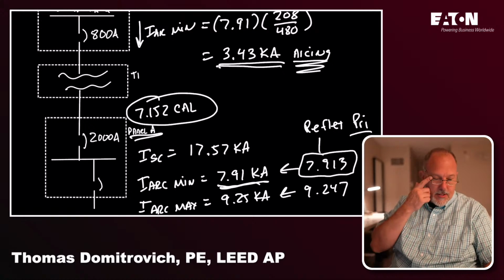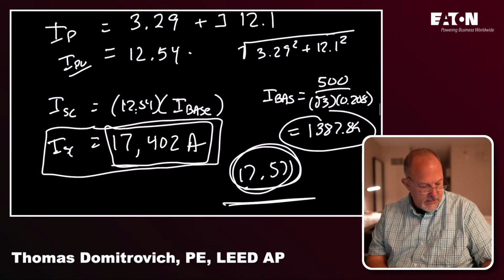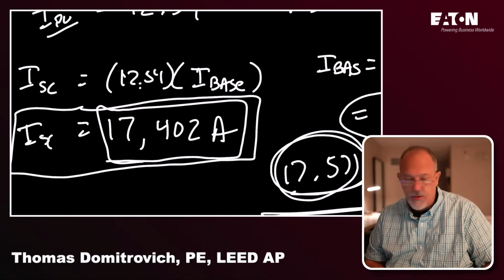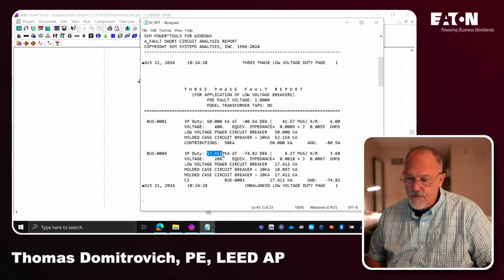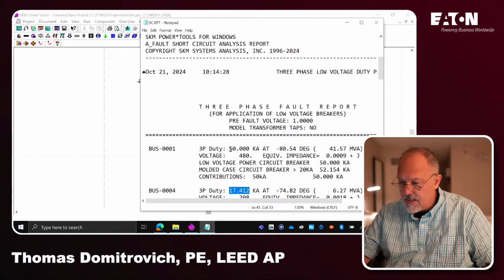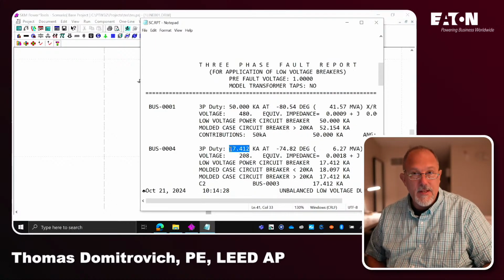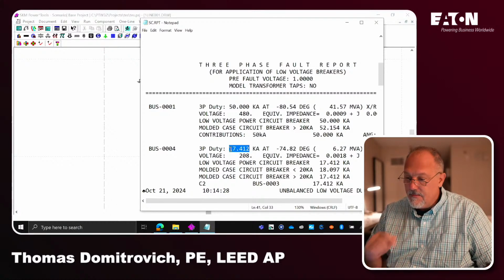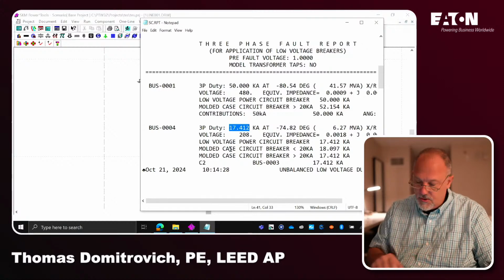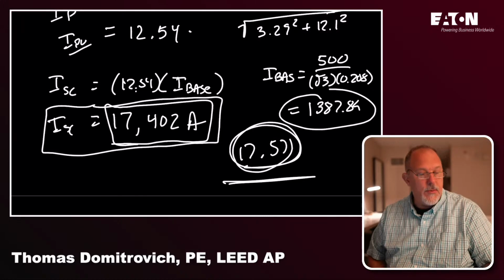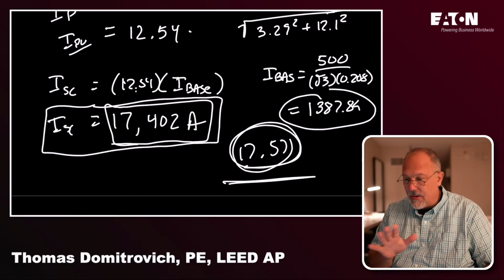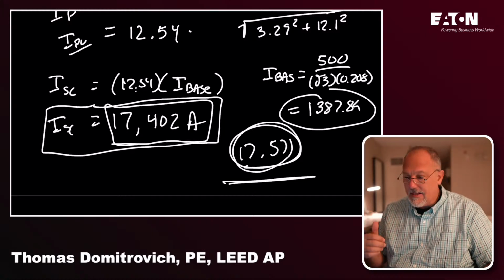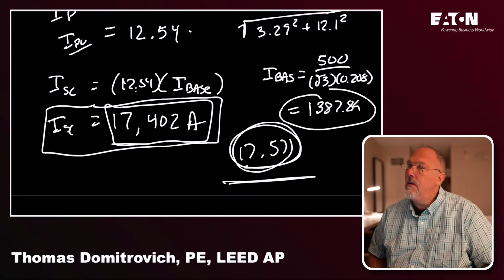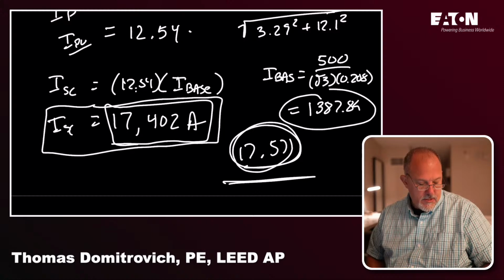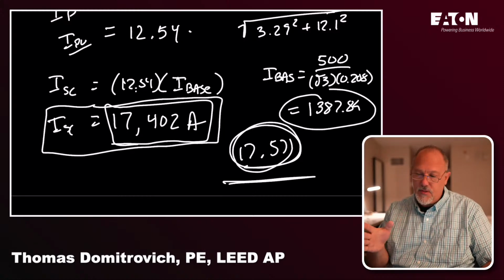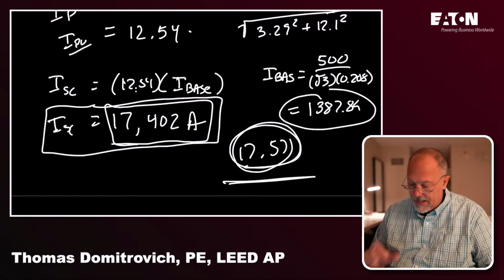Yes. All right, so remember our calculation. There's our short circuit, 17,402. And our calculation from this was 17,412. So this is pretty doggone close, right? 17,412 as opposed to 17,402 amps. So I got a little bit higher, 10 more amps using the SKM software as opposed to my hand calculation.